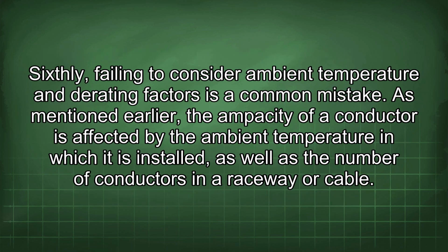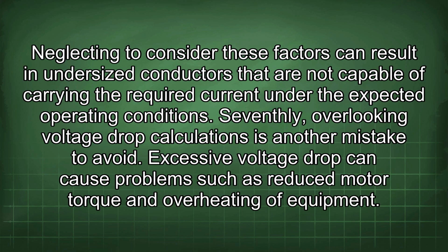Sixthly, failing to consider ambient temperature and derating factors is a common mistake. As mentioned earlier, the ampacity of a conductor is affected by the ambient temperature in which it is installed, as well as the number of conductors in a raceway or cable. Neglecting to consider these factors can result in undersized conductors that are not capable of carrying the required current under the expected operating conditions. Seventhly, overlooking voltage drop calculations is another mistake to avoid.